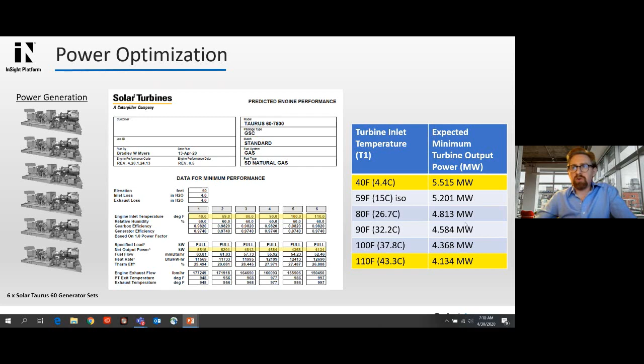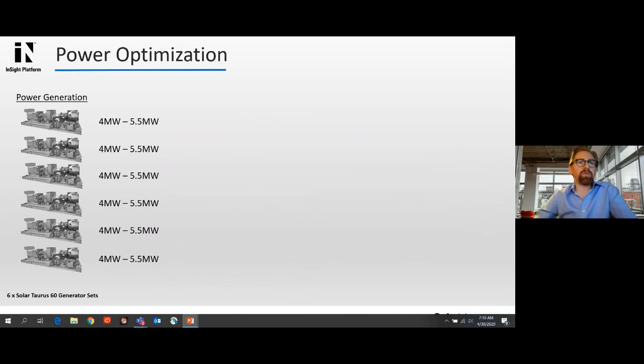A Taurus 60, looking at our typical 7800 engine rating, I've done calculations for different T1 temperature ranges, the ambient temperature range from 4 to 43 degrees C. We'd typically expect output power anywhere between 4.1 to 5.5 megawatts for our standard combustion application. So for all intents and purposes, I'll refer to each Taurus 60 as capable of between 4 and 5.5 megawatts.